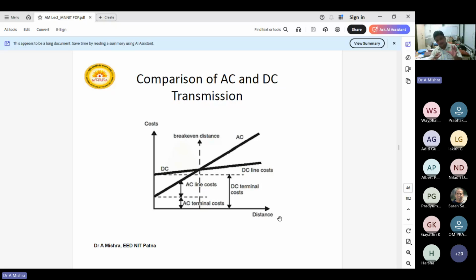How? All the three things are divided basically into three parts. First is the terminal equipment cost. Terminal equipment cost means, in the case of AC, your terminal equipment cost is less, because you need only a transformer and so on. The transformer is already part of the system, and you need relays, circuit breakers, all that, but those are the small parts. The second cost in AC transmission will be line cost. Line cost means the transmission line, number of conductors, towers and all. So line cost and terminal equipment cost, I'm not including the operating and running cost. That is basically included, but I'm discussing with you the initial cost.